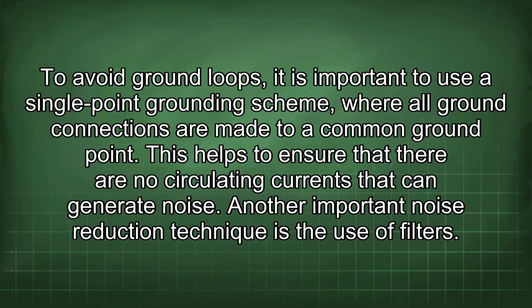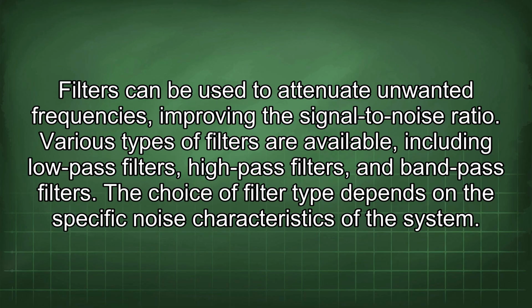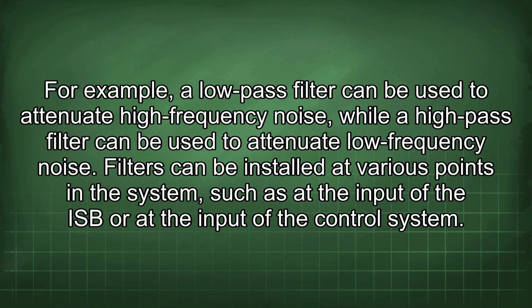Another important noise reduction technique is the use of filters. Filters can be used to attenuate unwanted frequencies, improving the signal-to-noise ratio. Various types of filters are available, including low-pass filters, high-pass filters, and band-pass filters. The choice of filter type depends on the specific noise characteristics of the system. For example, a low-pass filter can be used to attenuate high-frequency noise, while a high-pass filter can be used to attenuate low-frequency noise. Filters can be installed at various points in the system, such as at the input of the IS barrier or at the input of the control system.